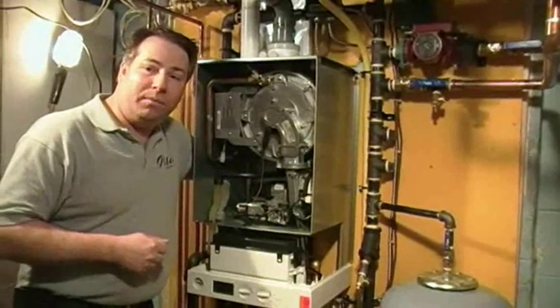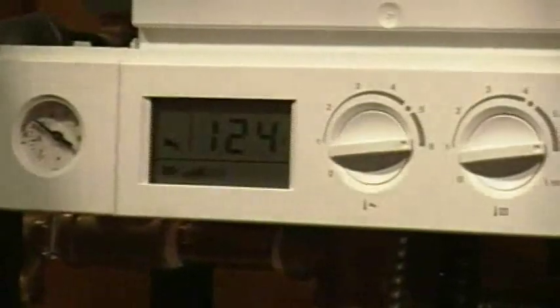I'm going to just give you a quick demonstration of the domestic hot water production that comes out of this boiler. We're going to draw some domestic hot water, and I'll show you how quickly the system responds to the draw. Right now we're at 123 degrees Fahrenheit, and we just had a call, which is the tap symbol, and the boiler is fired up almost within 2 seconds of the initial draw of water. And right now we are at about 127 degrees.